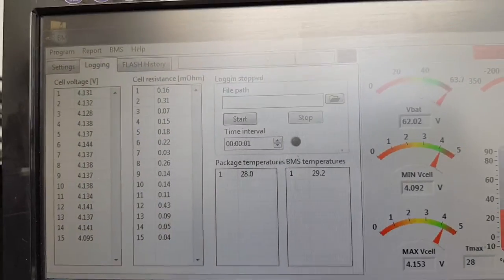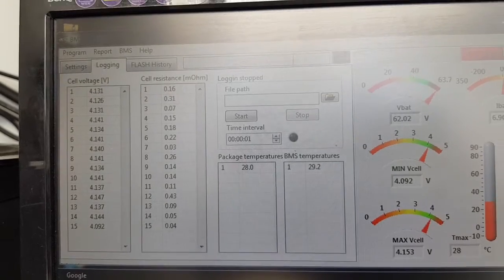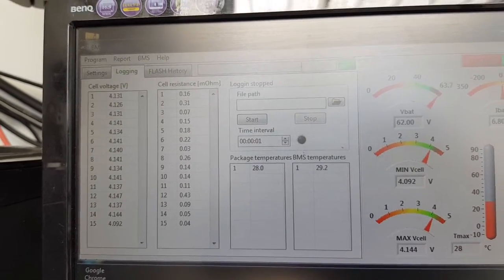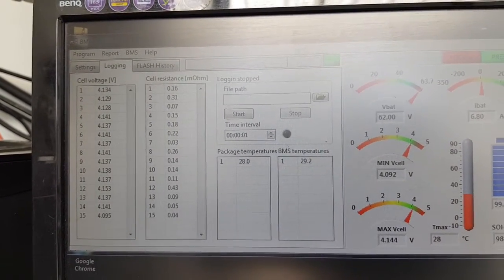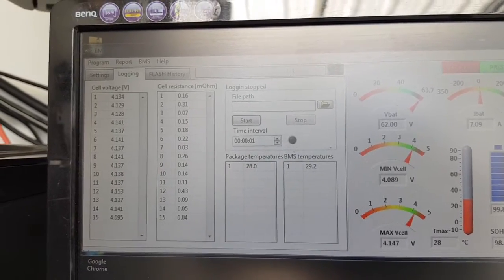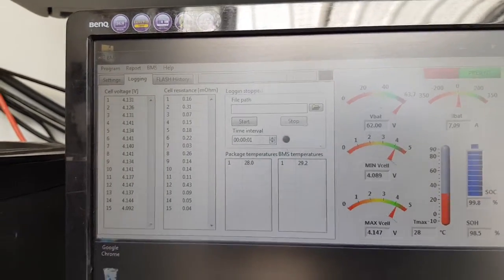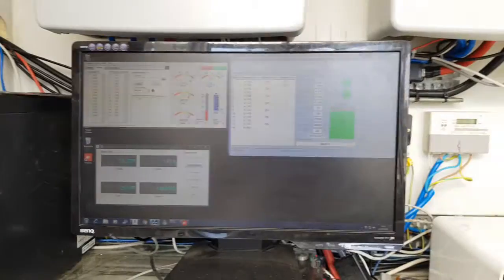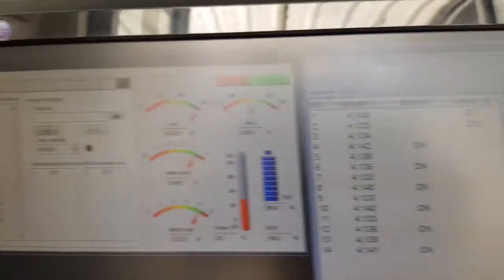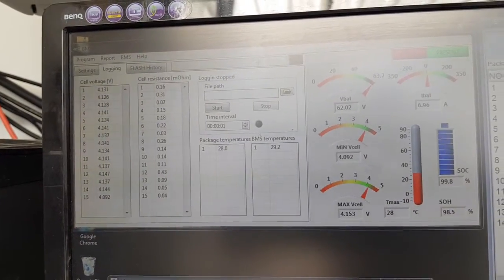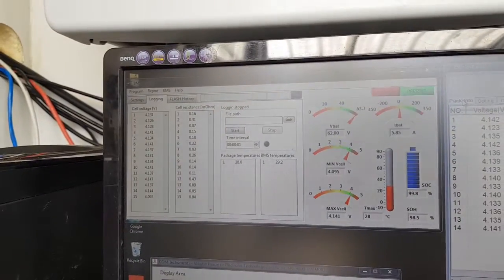You can see at the bottom, cell 15, that's the dummy cell I was talking about, so that's not really doing anything. But the system works, so it might say 62 volts, whereas we know, take one cell out, really you're more like 57.9 and not 62. But the point is, at least now it will charge to 100%.